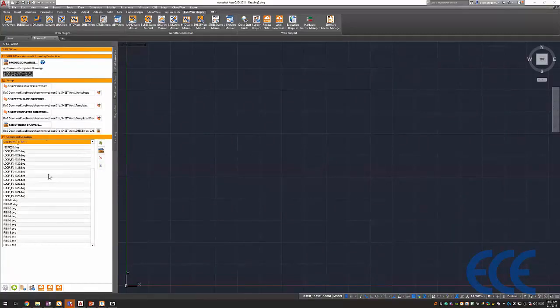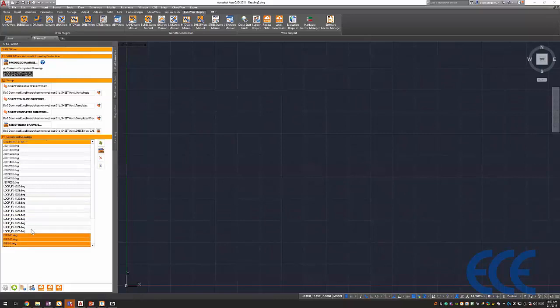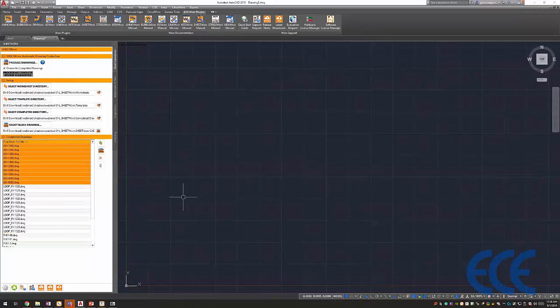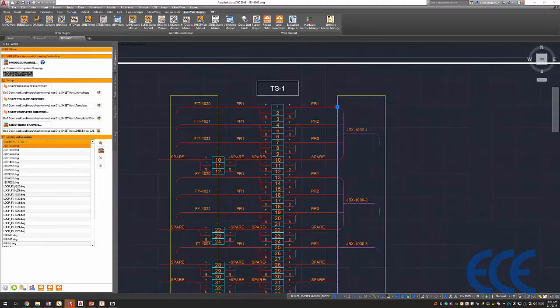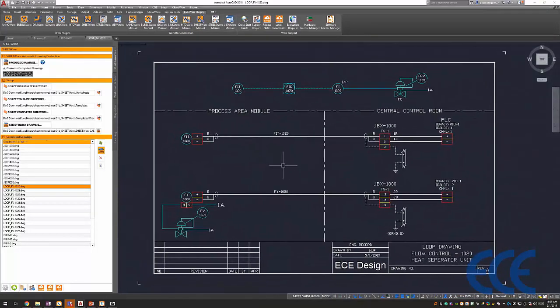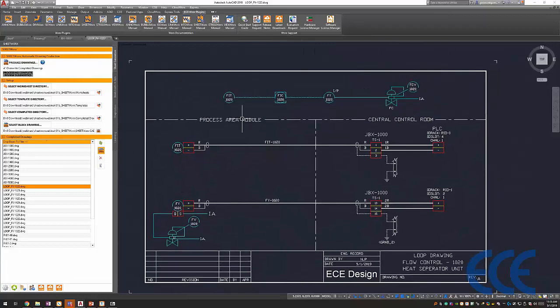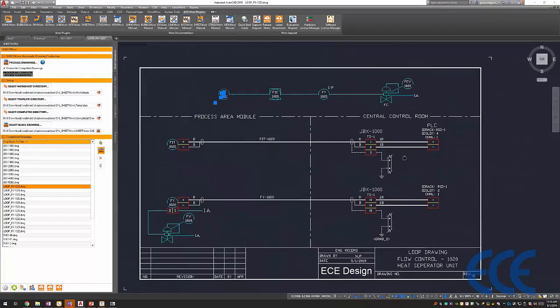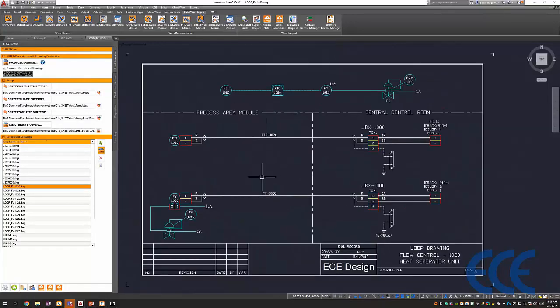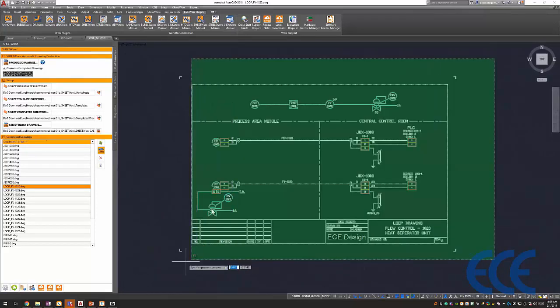It looks like it's almost done. I don't know how long that was, maybe like 10 seconds. But I've got 10 remote I/O drawings, 12 or 13 loop drawings, and 10 junction box drawings that were just created. Let's take a look at a couple of each. I'll go into a loop drawing so you can see one of those. This is a little bit simpler, these loop drawings, because there's not really positions for each block. What is unique here is that all of the information that you're looking at that's attribute driven is populated from Excel.